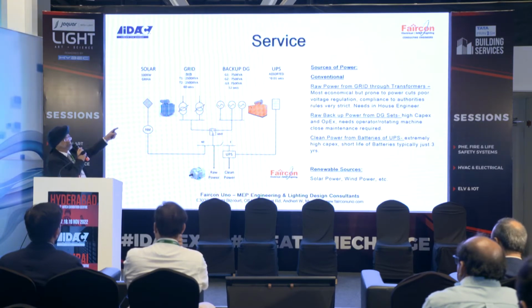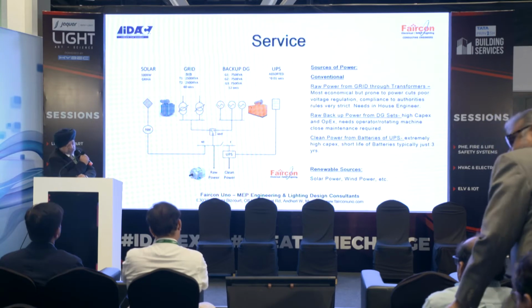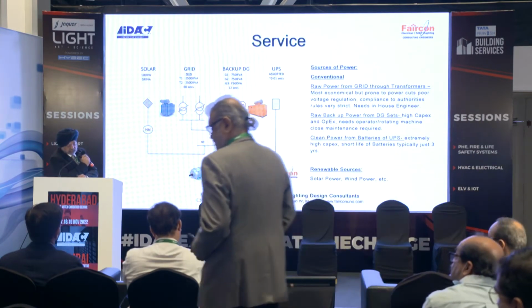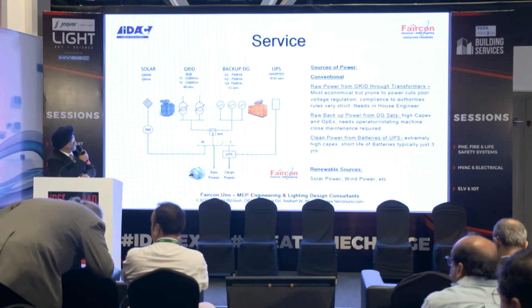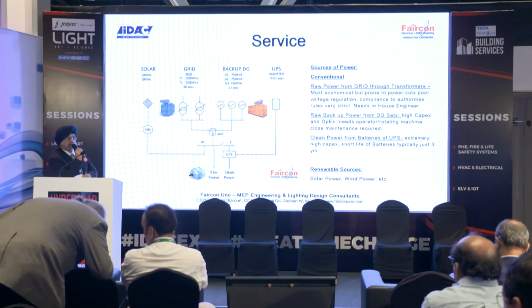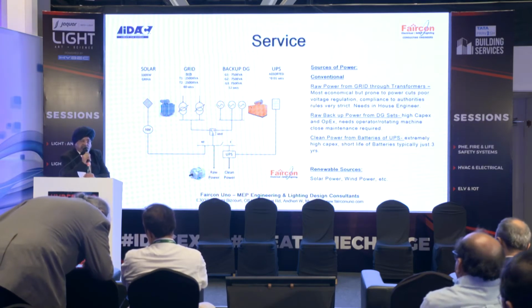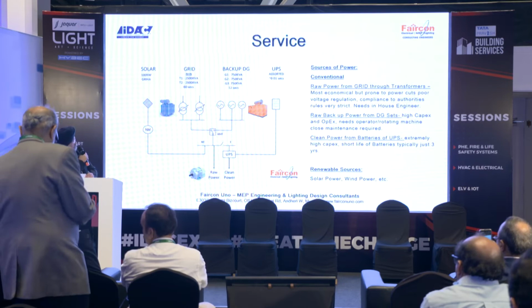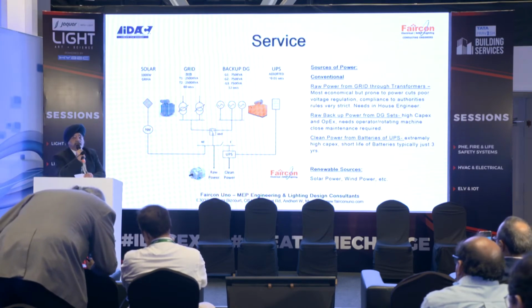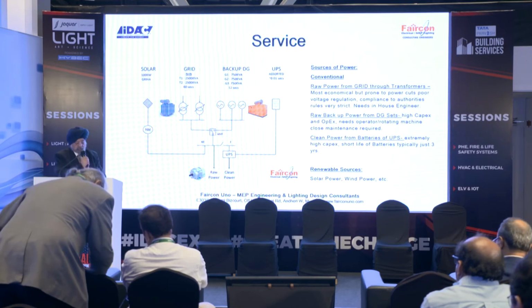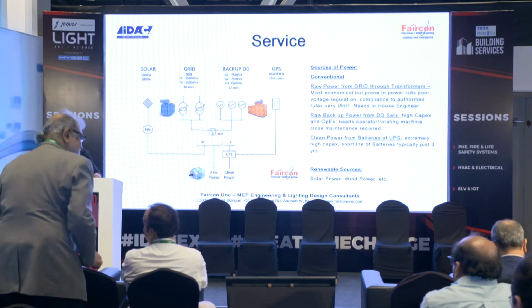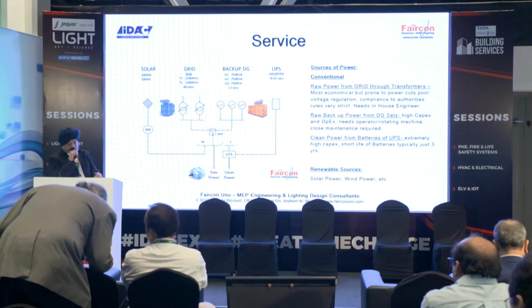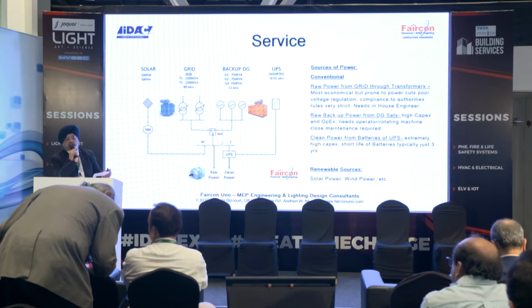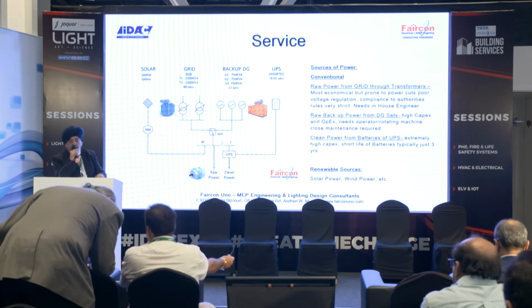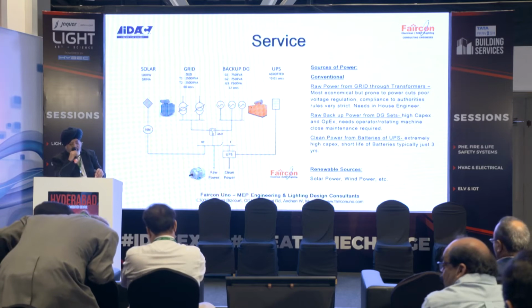You can see the transformers are with OLTC and the generator is with AMF and synchronization panel. An advantage of UPS batteries feeding the load is not only the speed at which it corrects the situation, but also that it gives you clean power. This is the key word, clean power. Now, what I mean by clean power is there are no harmonics, there are no surges, and it is a pure sinusoidal waveform. There is no distortion. So you don't have to worry about harmonics.